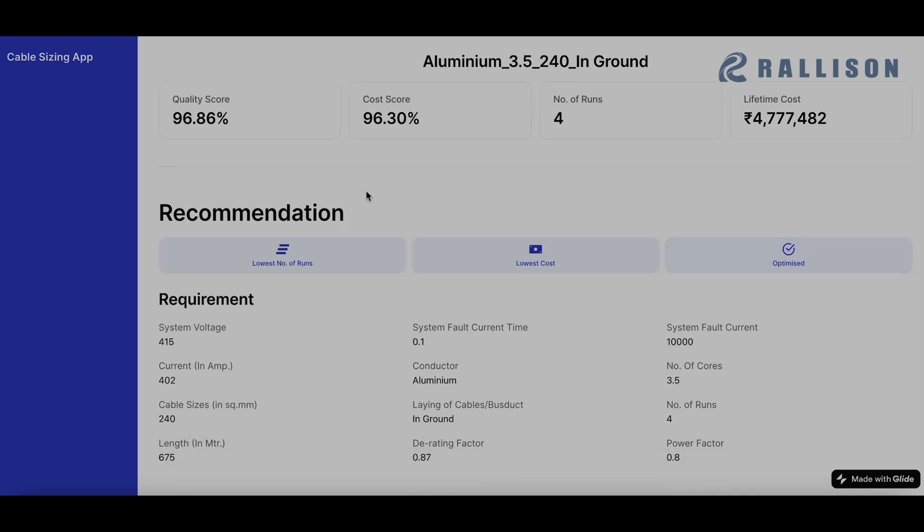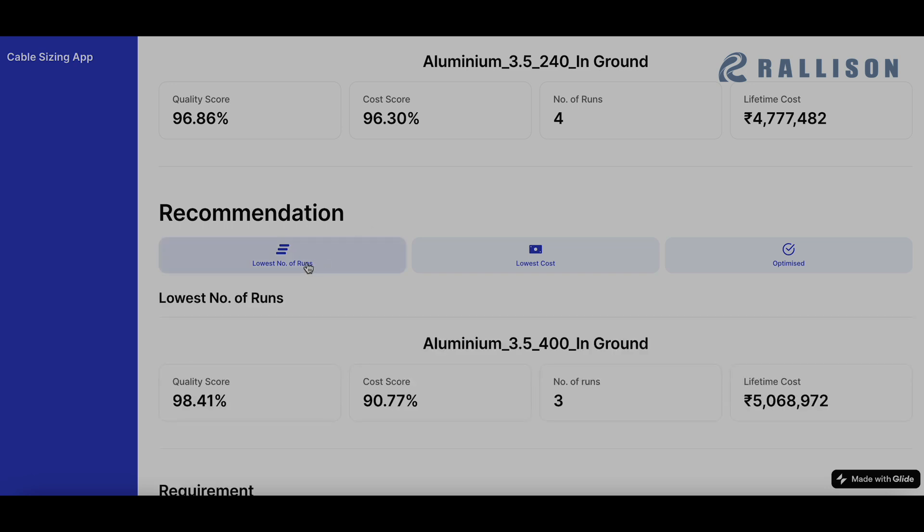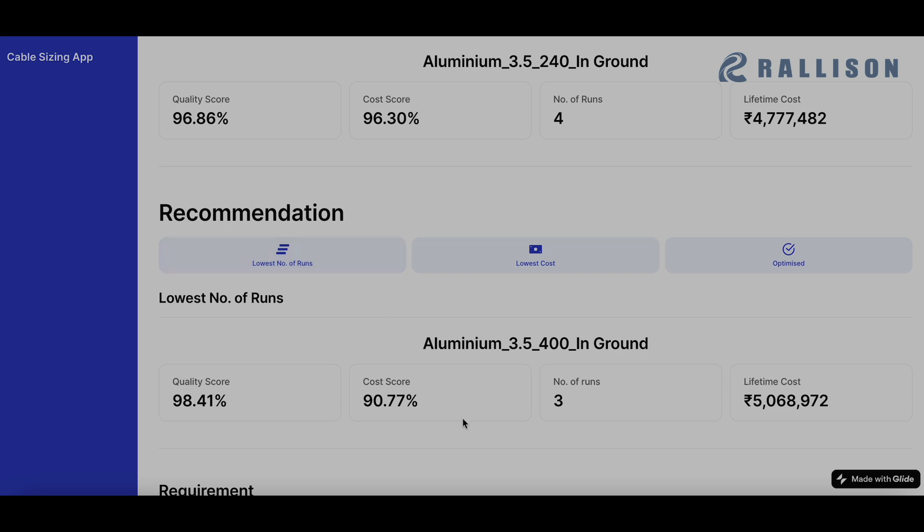Now when we go into the recommendations, this is what the app is offering as recommendations. So it can be based on various factors. The first one that we have clicked are the lowest number of runs. So say the designer wants to say that I don't want the lowest cost. What I want is the minimum possible number of runs because that makes handling much easier. So they can simply choose lowest number of runs and you see the recommendation is 3.5 for 400 with number of runs being 3.